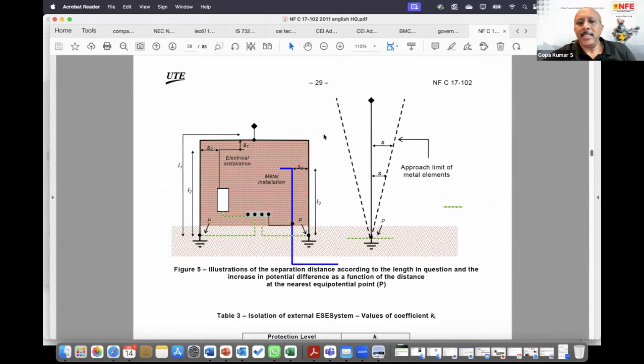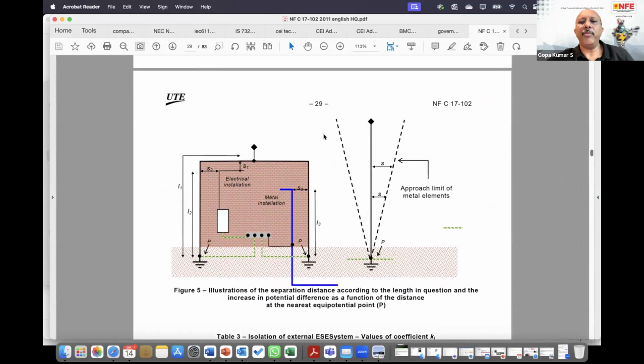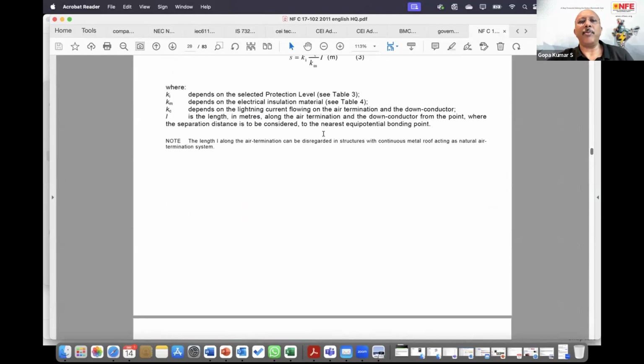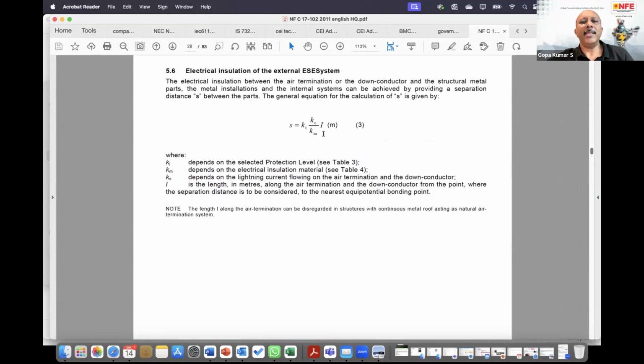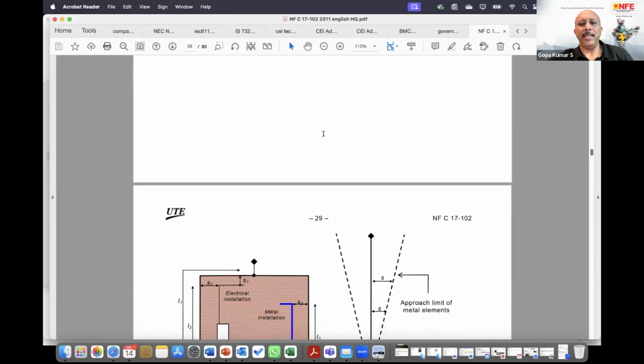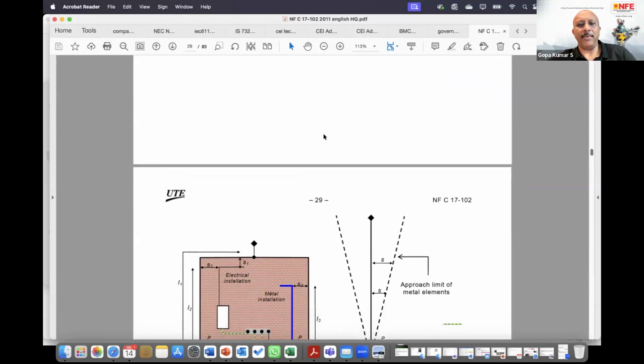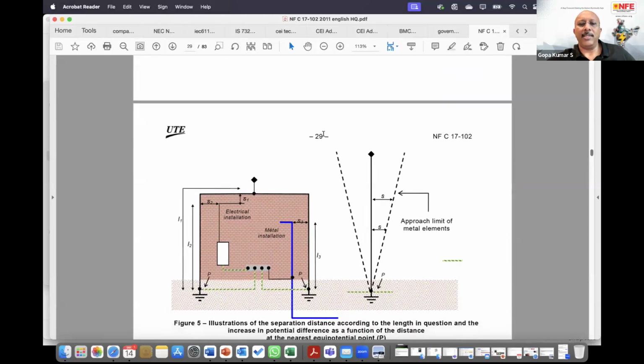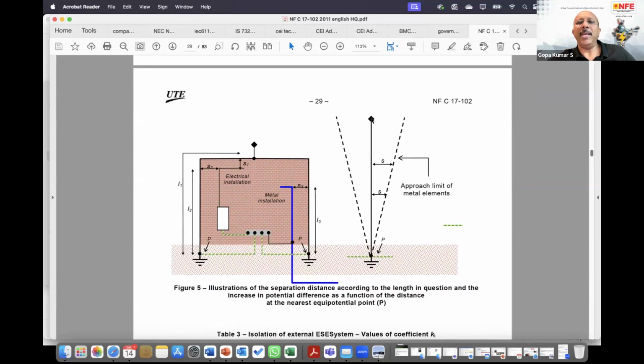This part of the ESE standard explains that if you have a single down conductor or, let's say, 2 down conductors, or if you have an insulated down conductor, not equipotentially bonded, you have to calculate the separation distance as per the French standard, NFC 17102, which is also the 62305, and you must keep the ESE and the down conductor physically away from the building. You can see here the approach limit of metal elements in the building. S means separation distance. You have to have a physical separation.